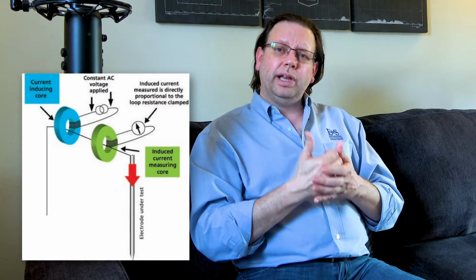And if you recall, a clamp-on ground resistance meter has 2 Rogowski coils. Right? One of them's active and one of them's passive, and it's going to induce a current. And what we see, instead of this long distance kind of continuity check, is a local area continuity check. What do we mean by that? So we're at our substation.